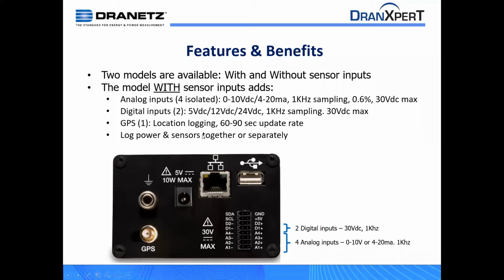When you choose the model with sensors, you also get a GPS connection on the back, and you would have to purchase an optional antenna. But what that provides are really 2 things. It provides time synchronization and location. So primarily time synchronization, so you know your meter is synchronized and the time is correct, as well as location, which I will demonstrate later, and you know where your meter is. If you put it out in the field somewhere, you know where that substation may be or whatever it is.